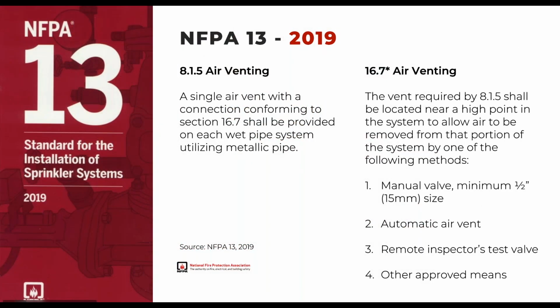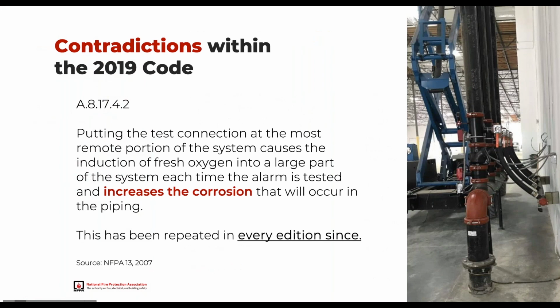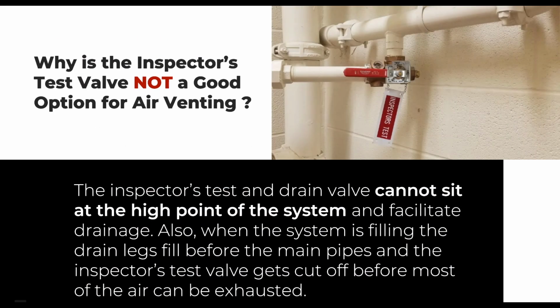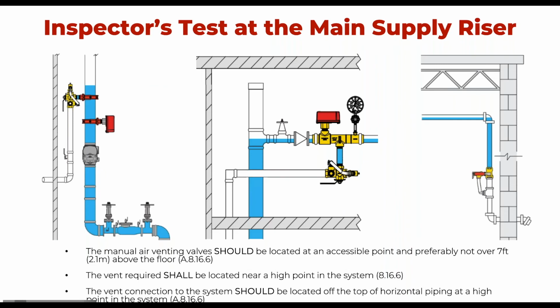NFPA 13 in 2019 added an option of the remote inspector's test valve. I bring that up as a caution that it's something that's being addressed because it caused a conflict. In one section of the same code, in the same chapter, they say that you should move the remote inspector's test to the supply because a remote inspector's test will let in new air. Well, then it doesn't make much sense that the remote inspector's test would also let out the air. So that was just a poor choice of how they located and worded this allowance.